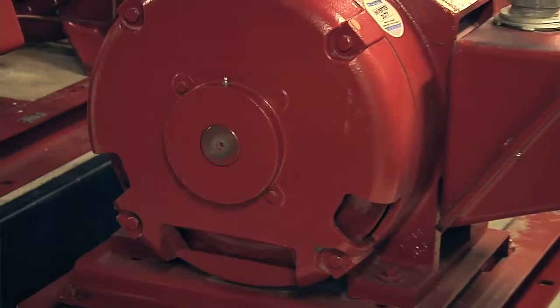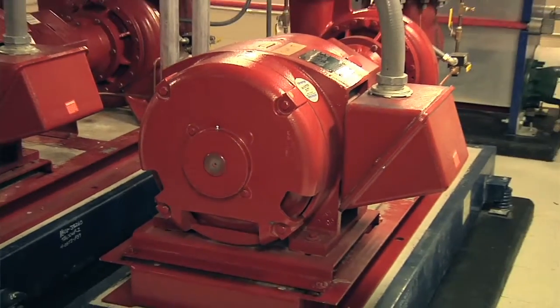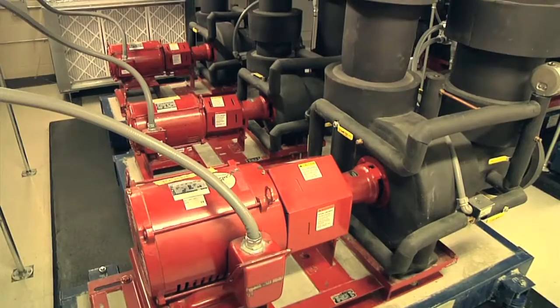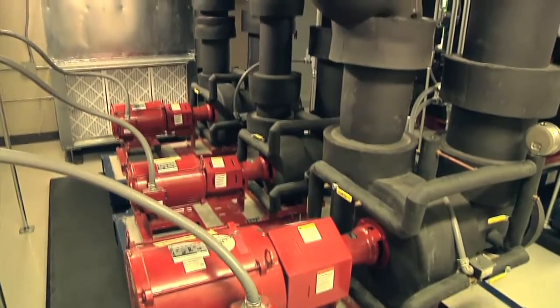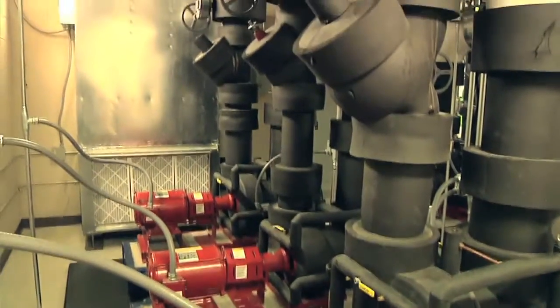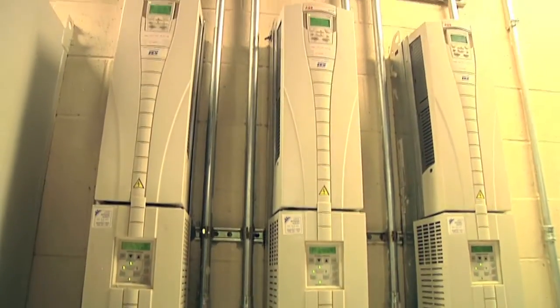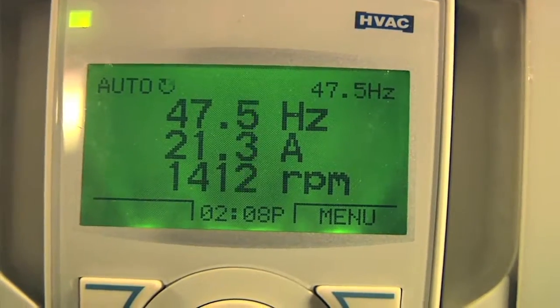this project. We have a pump dedicated just for each chiller, but then we have pumps that are dedicated for the chilled water side that after the water has been conditioned, it boosts the pressure to get the water up to the 16th floor. All these pumps are operated on variable frequency drives to match load at all conditions.